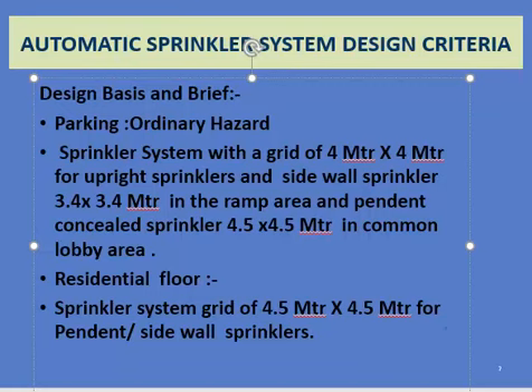Continuing with sprinkler design criteria: in parking areas classified as ordinary hazard, sprinklers are placed on a 4 meter by 4 meter grid. Sidewall sprinklers are placed at 3.4 by 3.4 meter spacing, and concealed sprinklers are placed at 4.5 meter grids in lobbies. Residential floor sprinklers are spaced at 4.5 by 4.5 meter grids.